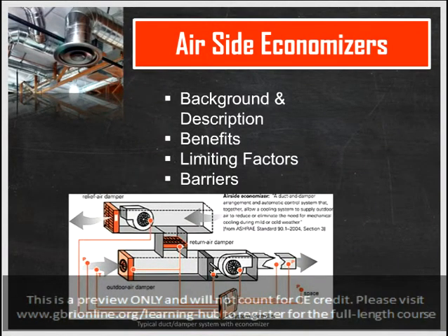Airside economizers refer to the use of additional outdoor air when conditions are favorable to supplement or replace the cooling or heating equipment. For example, when the ambient temperature outside is cool, colder than the indoor temperature, outdoor air can be introduced to manage the cooling load instead of the compressor to condition the air. Obviously, this will only work when outside air conditions are suitably cold and/or dry. Drawing in warm or humid outside air will increase the cooling and dehumidification load on the HVAC system, increasing energy consumption. There are typically 4 operating modes for an airside economizer.